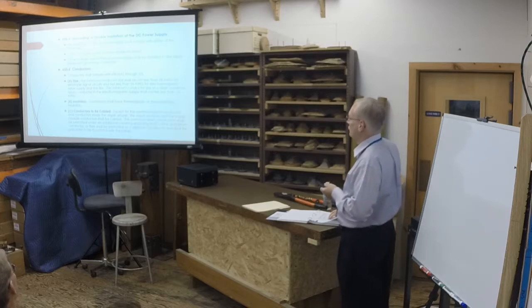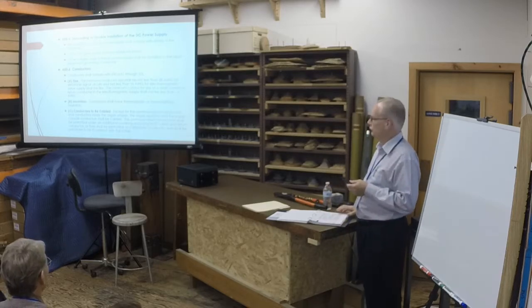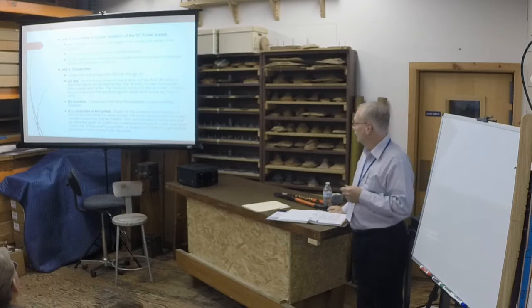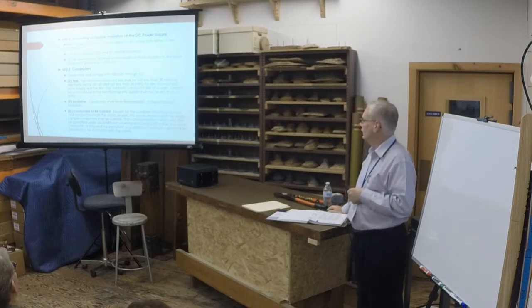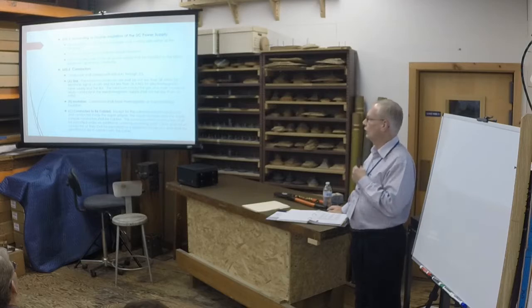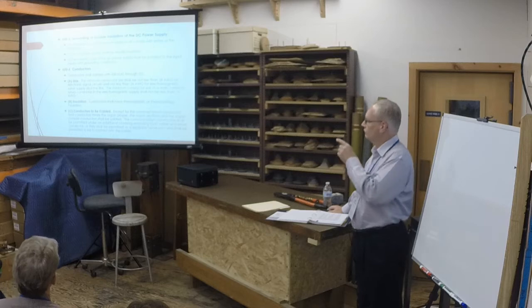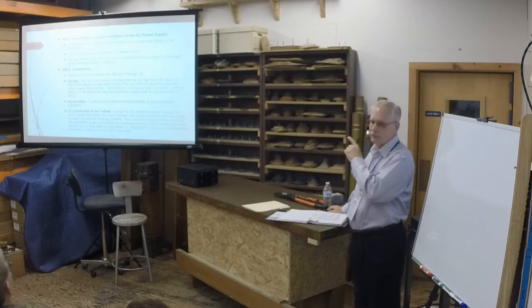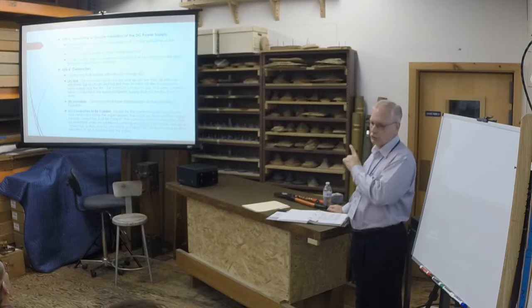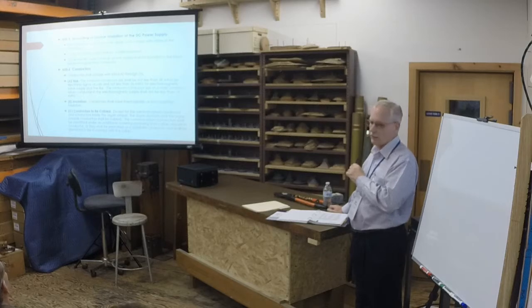Conductor size, and this is a change, which is kind of interesting. Minimum conductor size is 28 American wire gauge. Pay attention to that, because it says for signaling, non-resistive loads only. You cannot drive a magnet with 28 gauge wire.